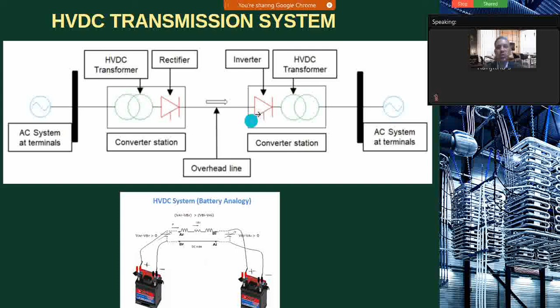Now here is a simple video showing different areas in the switch yard. This is the AC switch yard, these are converter transformers, then we have thyristor valves. This is the DC portion, and these are the harmonic filters, and sometimes shunt capacitors are also used to provide more reactive power if there is a deficiency of reactive power in the system. So this is the structure of conventional HVDC, that is current source converter based or thyristor based HVDC.